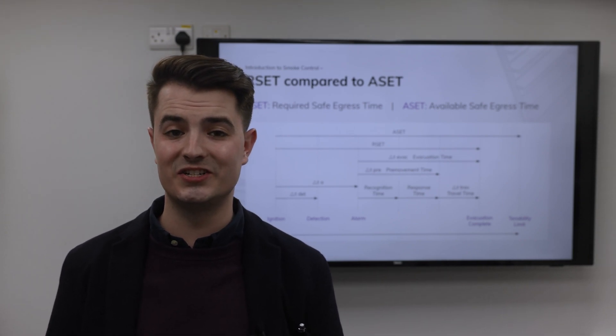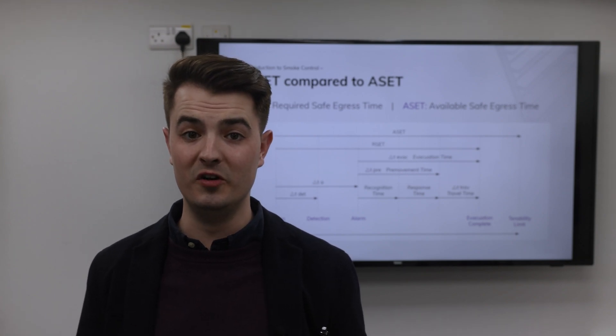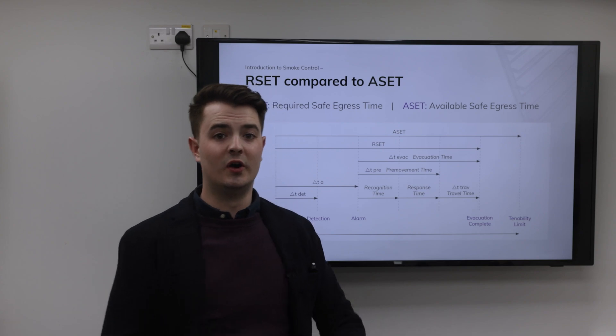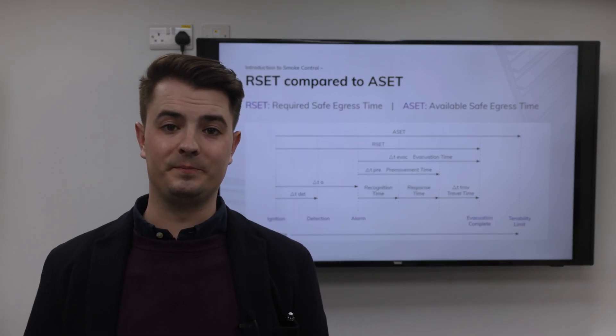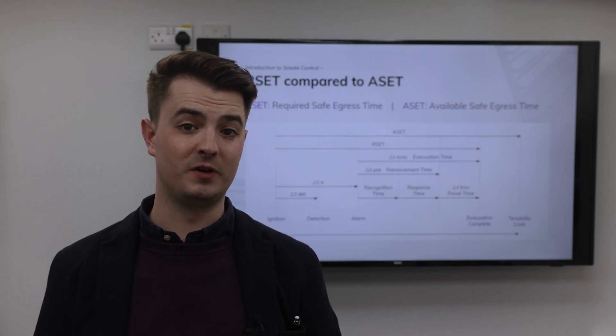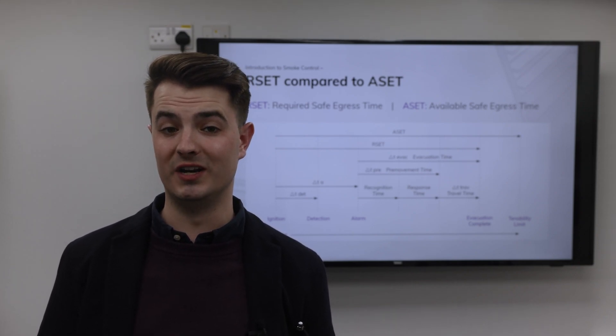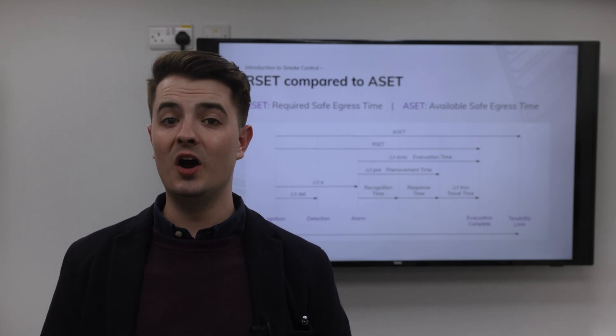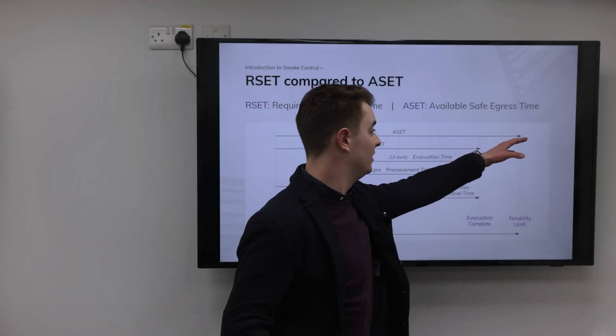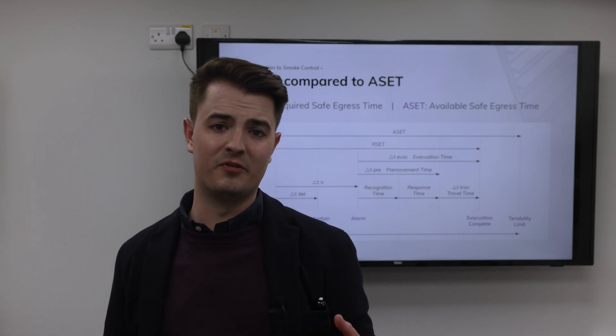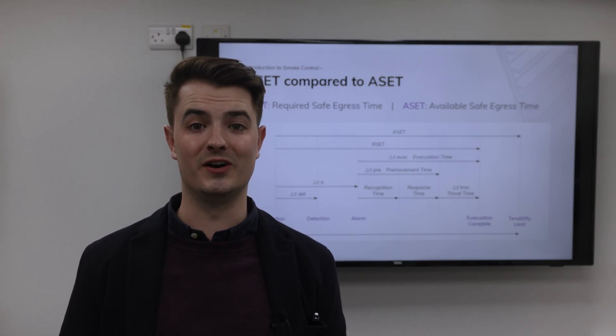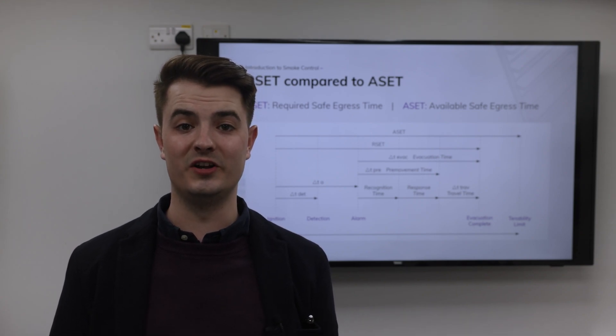By adding together the detection time, the pre-movement time, and the movement time, we get the RSET for the building. As this is a theoretical approach using computer models, the results are then multiplied by a safety factor to make sure it's as realistic as possible. Finally, we compare the ASET to the RSET, and provided the required safe egress time is shorter than the available safe egress time, then safe fire evacuation is ensured.